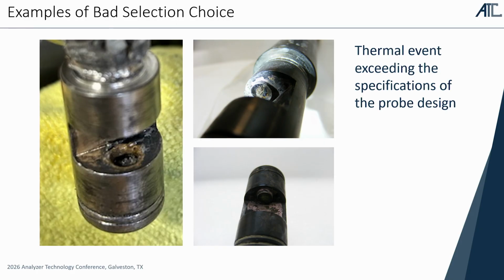So make sure that the temperature specifications that you're actually going to get are going to work. Did you wrap everything in heat tape? You set the heat tape to 60 degrees, but it just sits there and cooks, and you don't actually have temperature control over where your process point is at. These are expensive mistakes.